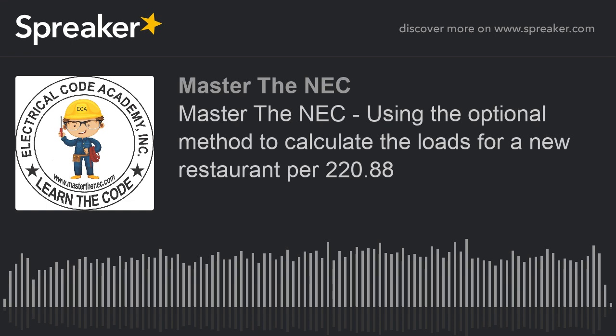Connected means the total loads simply added up. And the calculated is the calculated value after you apply some type of calculation, whether it's percentages, people call it demand values. Once you get a value after that, that is your calculated load, means you had to do something. The connected load is simply taking all the loads.